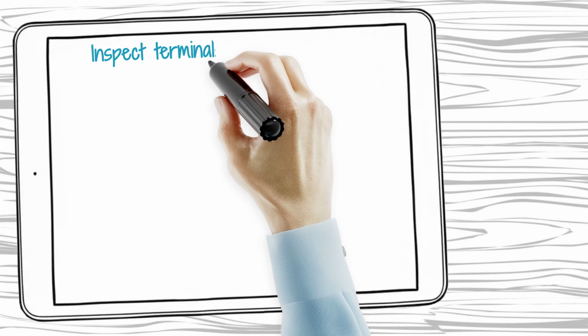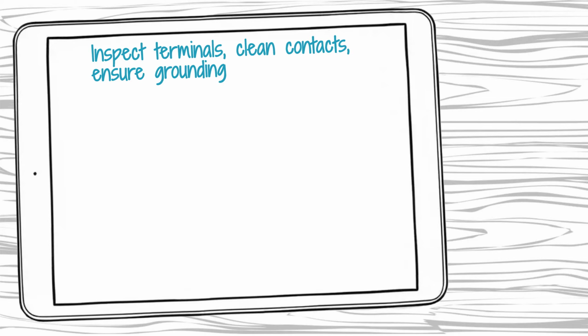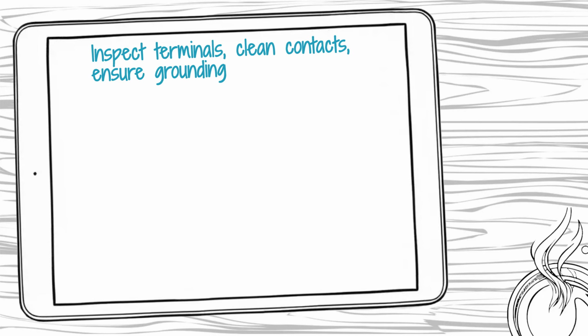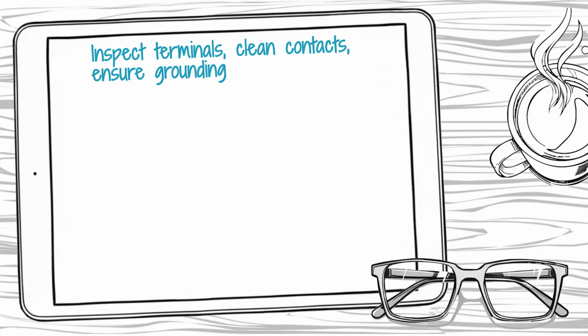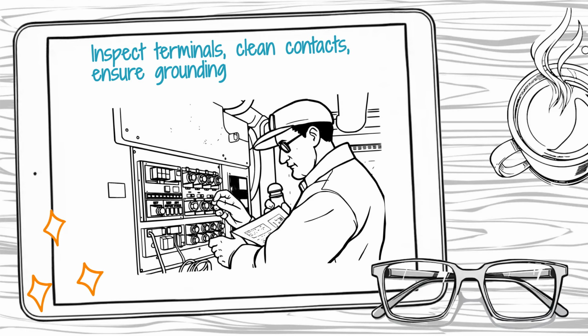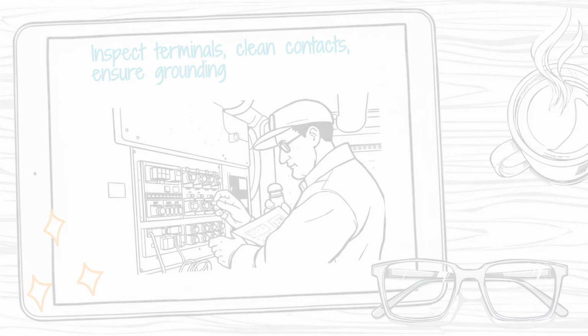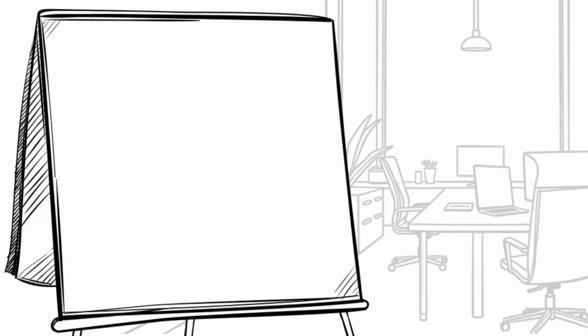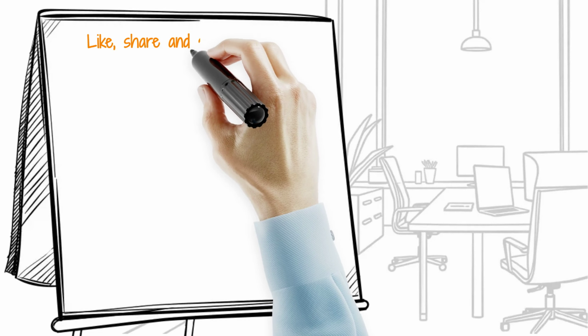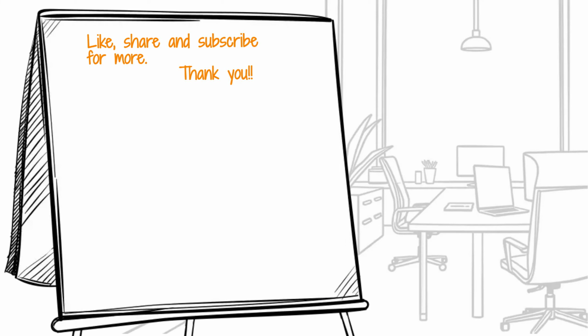Inspect all electrical terminals for corrosion or loose connections, as added resistance in the circuit is a common cause of false high-temperature readings. Use specialized contact cleaner on the junction points and ensure the shielding of the sensor cable is properly grounded to prevent electromagnetic interference. Once the calibration is complete, apply a fresh layer of thermal-conductive paste to the sensor tip before reinserting it into the thermowell to ensure rapid and accurate heat transfer.